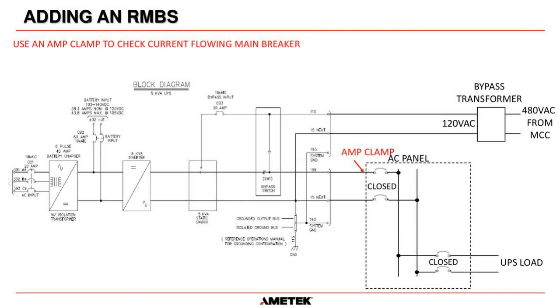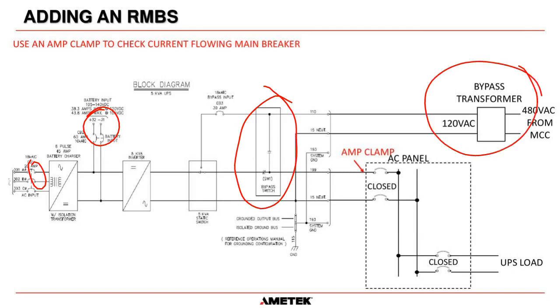Once again, we have our internal bypass switch here. We have our 3-phase AC coming in. We have our batteries here. And then on the right-hand side, we have our bypass supply. And that usually comes from an MCC at 480, and then it gets stepped down to 120 for most of our industrial UPSs that we use. Now, yes, it can be 208, 120, 3-phase, but that would just complicate these drawings if I did that. But most of the stuff that we do is 120 volt, single phase, okay?